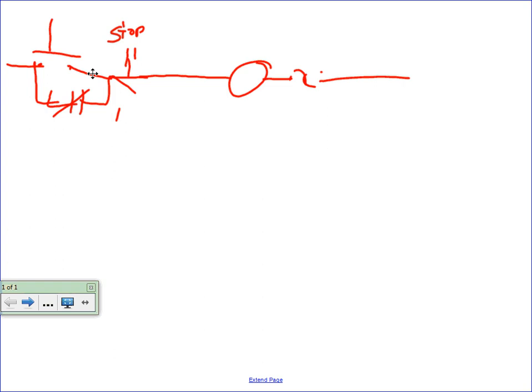So a soft start is an electronic device that slowly ramps the motor up to speed and slowly ramps the motor back down to stop. We use that in applications where a hard, full voltage start may be a disadvantage, like pumping applications. If you try to start that pump up at full speed, you get water hammer, which could cause pipes to burst. In an HVAC system, again, you overpressure the duct system and can blow it apart. So what a soft start does is give it a ramp up to full speed and a ramp back down.